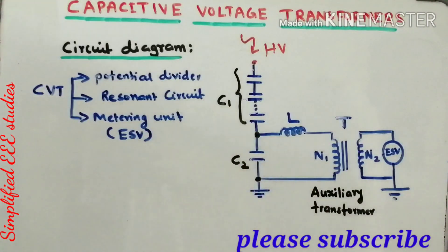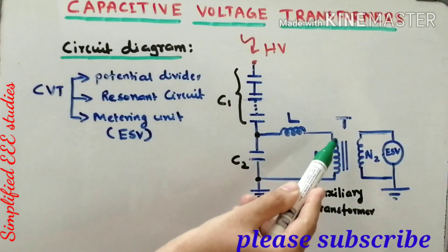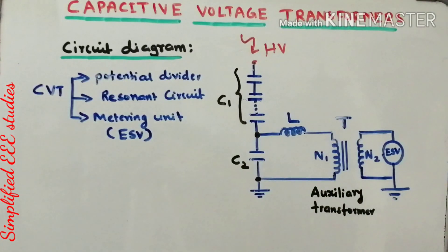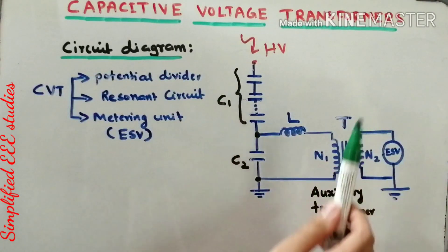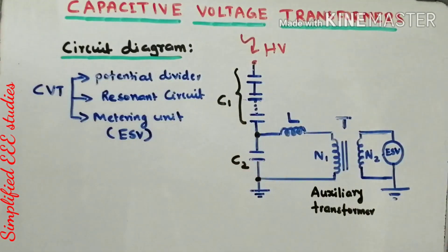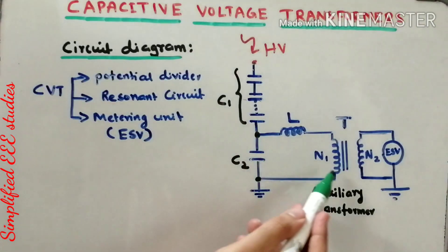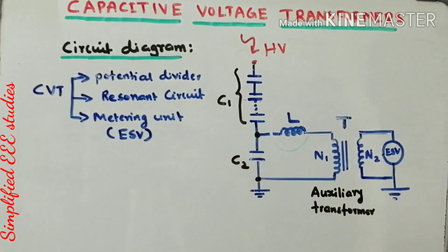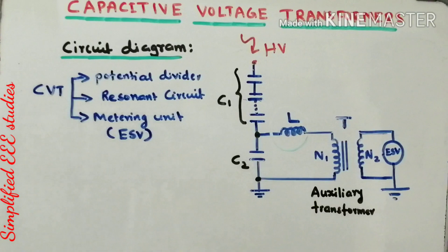The main function of the inductor: first, there will always be a voltage drop in the transformer. An isolation transformer, also called an auxiliary transformer, is placed here to maintain isolation between the input side and the output side — otherwise the meter will be damaged. To reduce the voltage drop of this transformer, the inductor provides suitable compensation for the auxiliary transformer. That is the primary function.